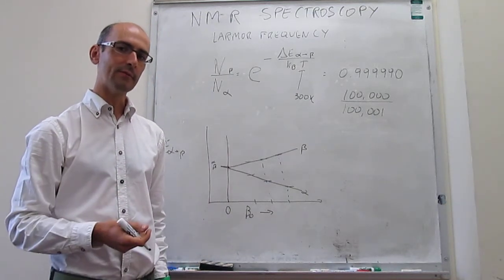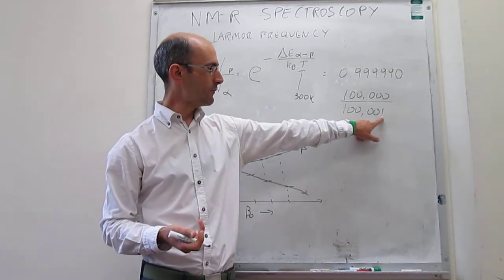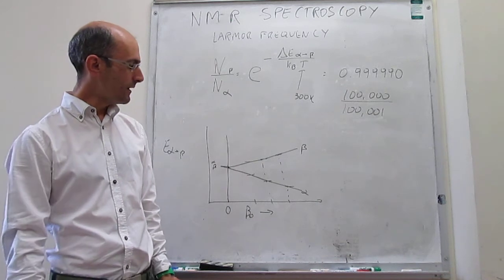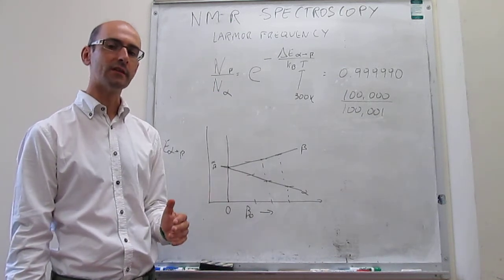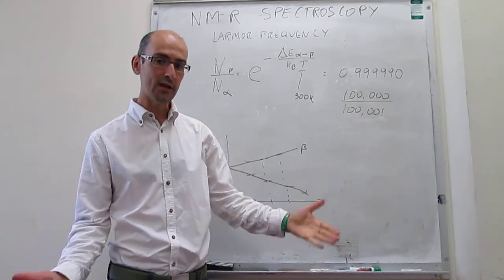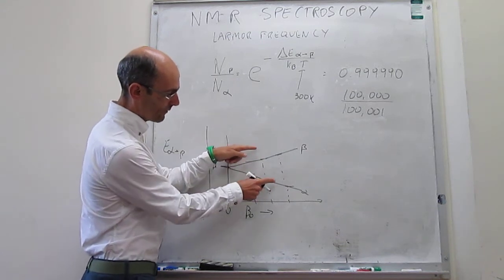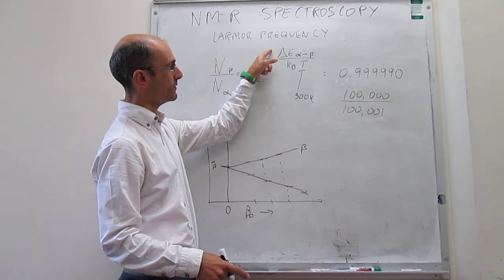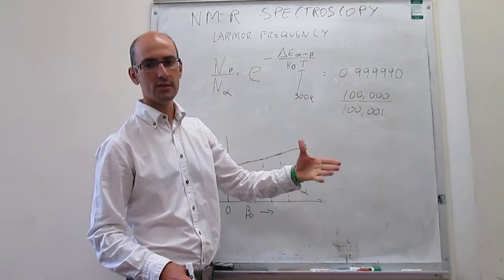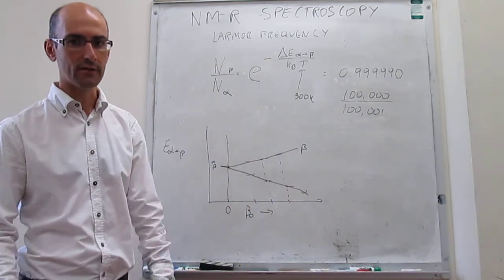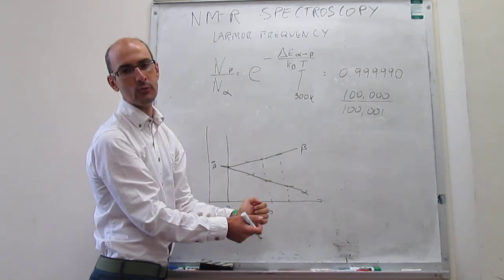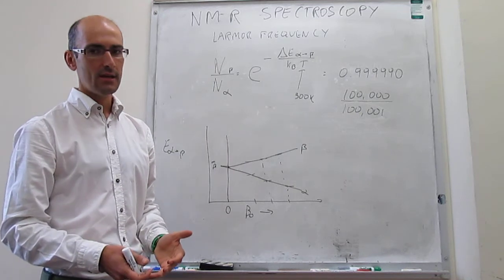The sensitivity and intensity of your NMR signal is proportional to this population gap. You want as much excess population in the ground state as possible, and a way to increase that is to increase the energy separation between the two states. The larger you make this energy gap, the greater the bias of population toward the ground state, and therefore the greater the signal intensity. This is one of the key advantages of using a large magnetic field versus a small one: large fields increase the alpha-beta energy gap, bias the population more toward the ground state, and make your signals ever more intense.